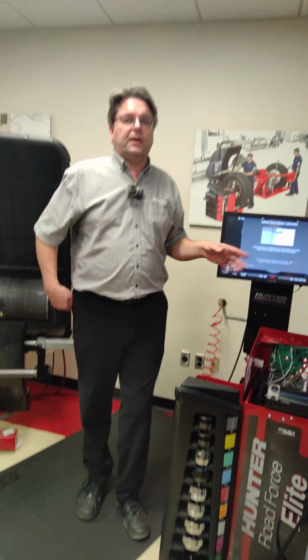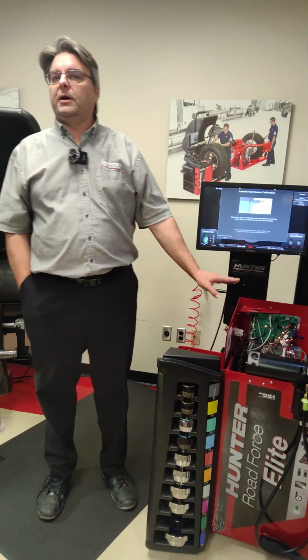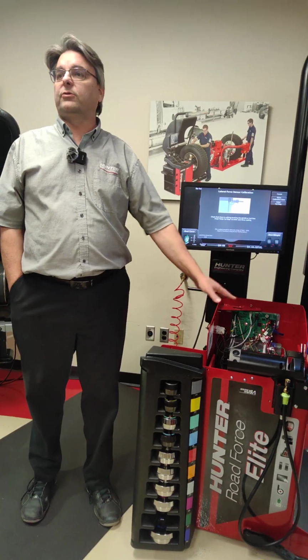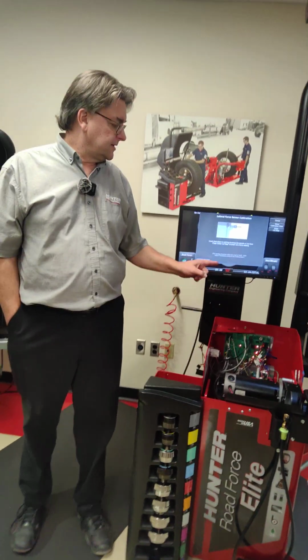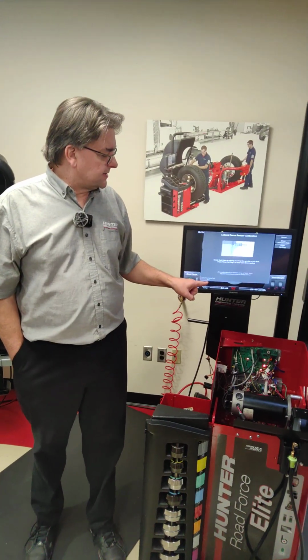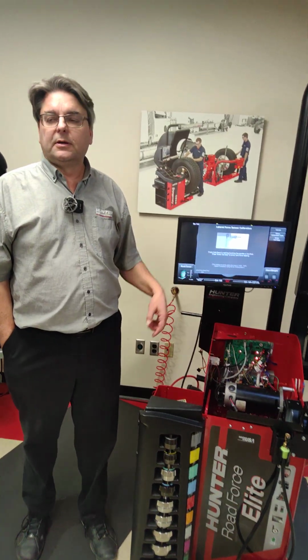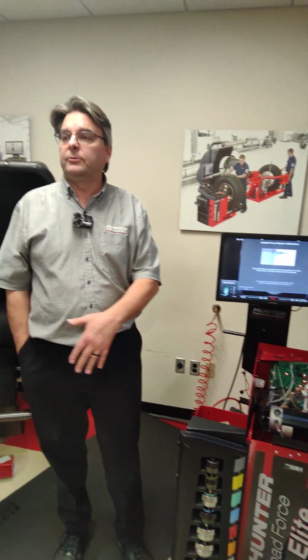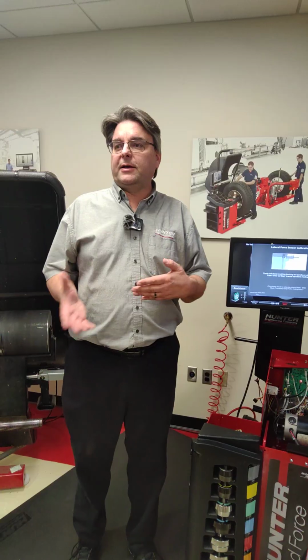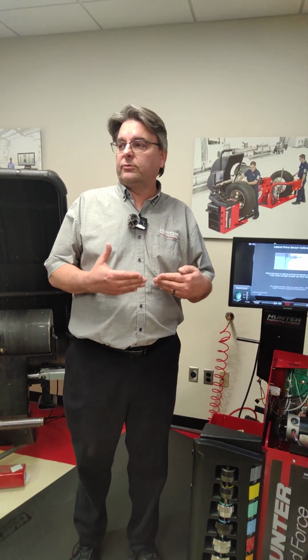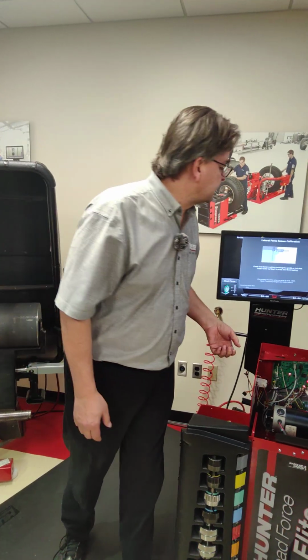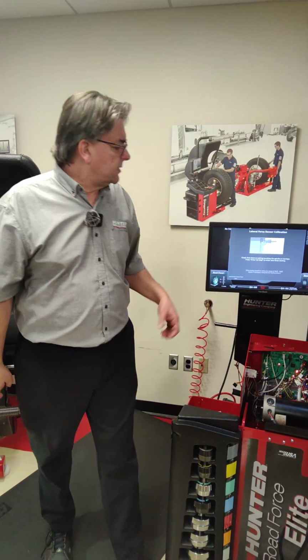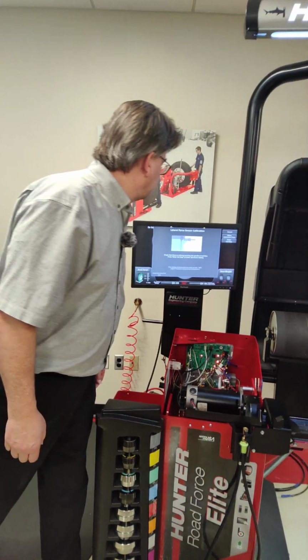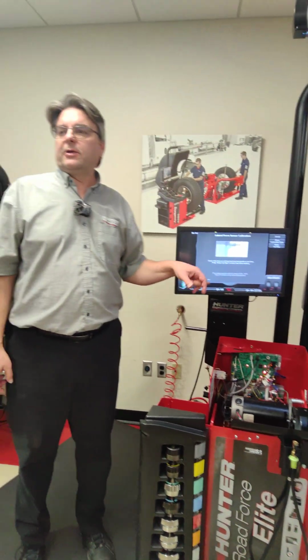So this unit to my left, your right, failed the lateral force calibration step because the lateral force number is not between those two. It was below the minimum. So we have to start out at a good known range so that we know what the tire pull is. And this thing here, instead of being at 56, is around 53, right? Well, it's down now because we loosened it. Okay, well that's fine. So anyway, it's about 300 counts off.